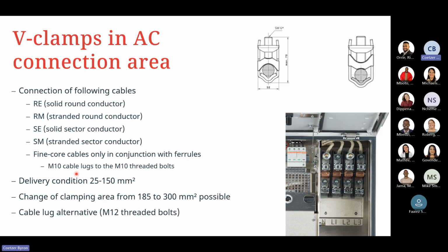So again, the delivery conditions: it's anything from 25 to 150 mil squared, and changing the V clamping area to accommodate 185 to 300 millimeters square cable coming in is also possible. So what we'll simply do is remove the V clamp, swap the orientation, and refasten it back in to allow us to mount either a smaller cable or a much larger cable.